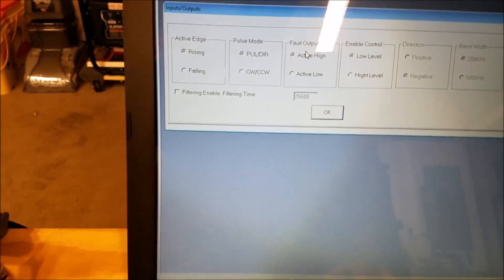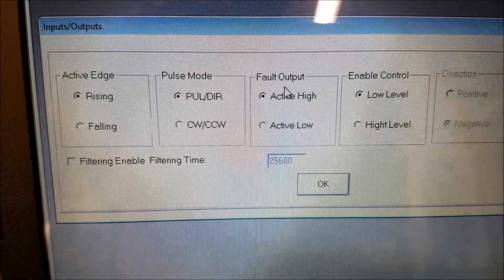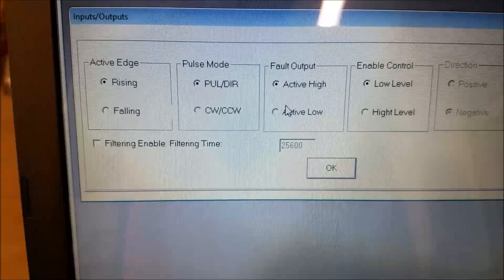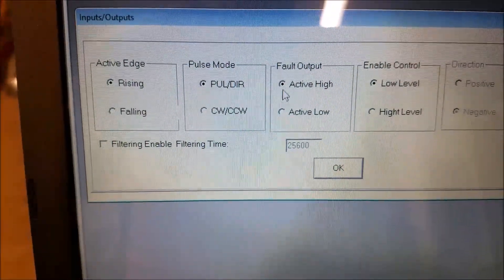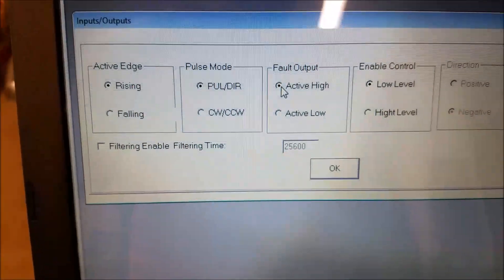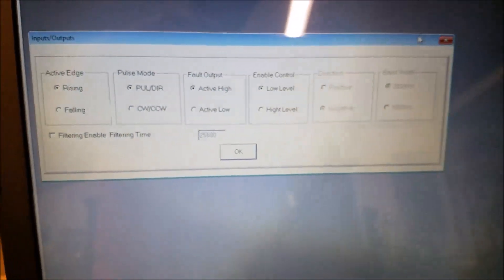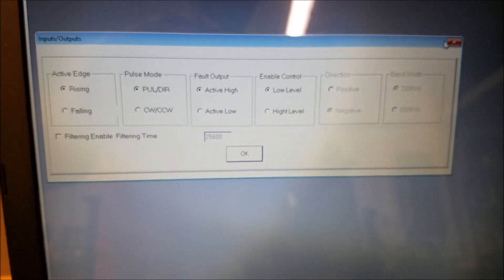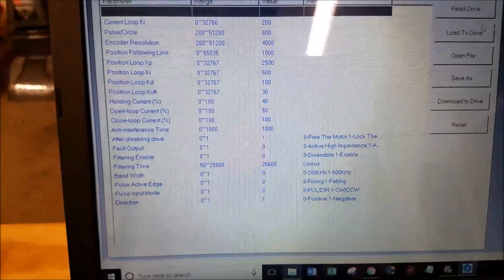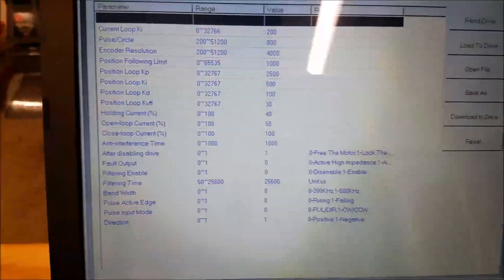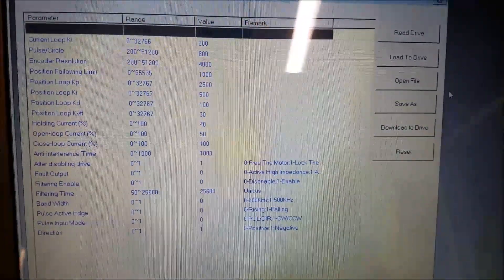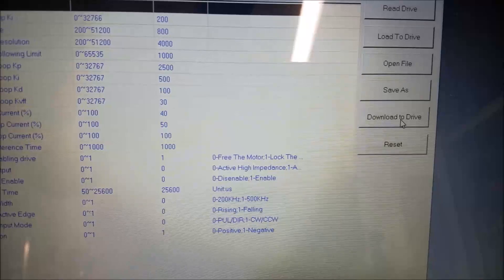So the one that I have to change is under IO. And what it is, is fault output. So fault output, every drive I've bought, it defaults to active low. You need to change it to active high and then say okay. And then what happens when you come back here, let's say read drive, just to give you the idea here. After you make that setting, you're not done. Even though it looks like it wrote something to the drive, you're not done.